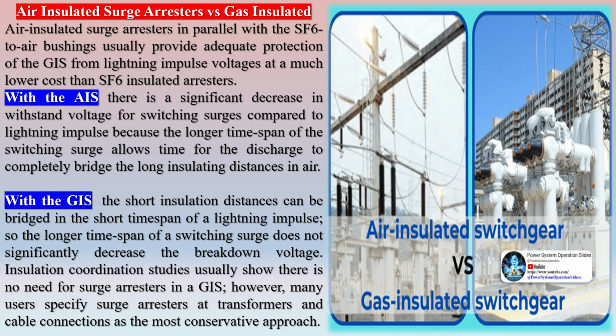With the AIS, there is a significant decrease in withstand voltage for switching surges compared to lightning impulse, because the longer time span of the switching surge allows time for the discharge to completely bridge the long insulating distances in air. With the GIS, the short insulation distances can be bridged in the short time span of a lightning impulse, so the longer time span of a switching surge does not significantly decrease the breakdown voltage.